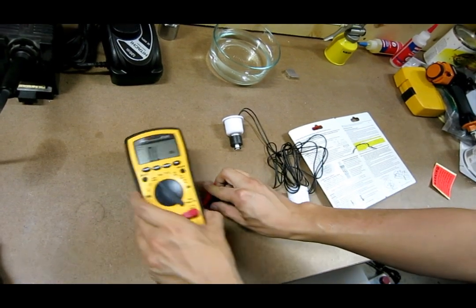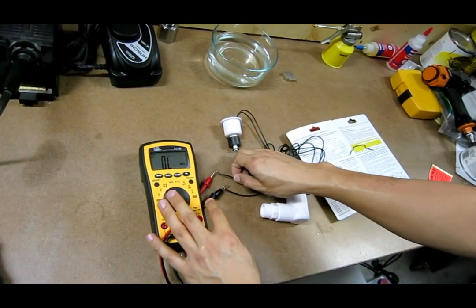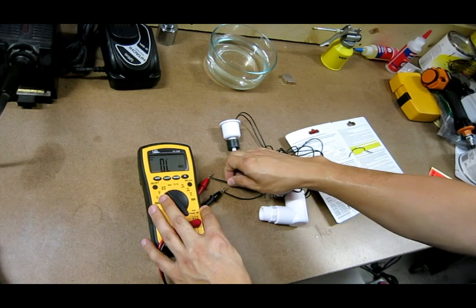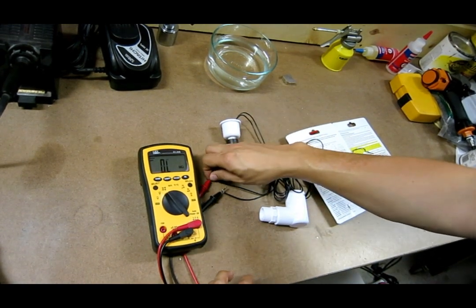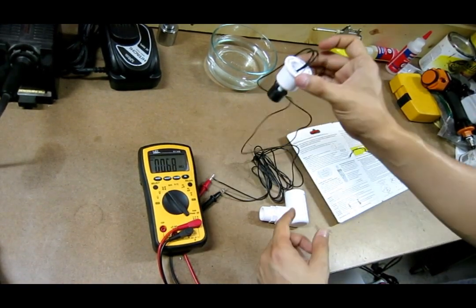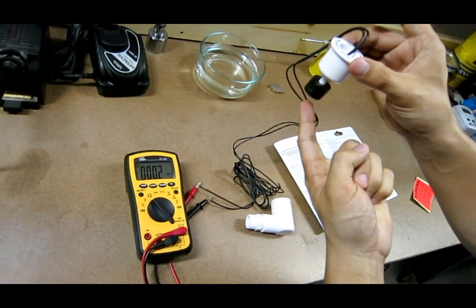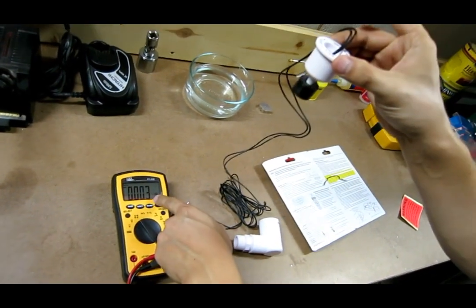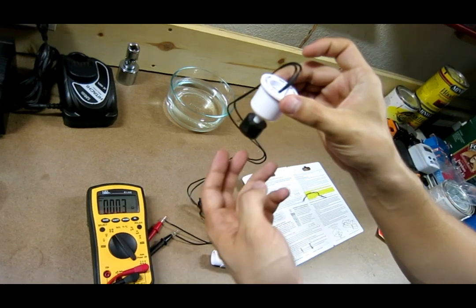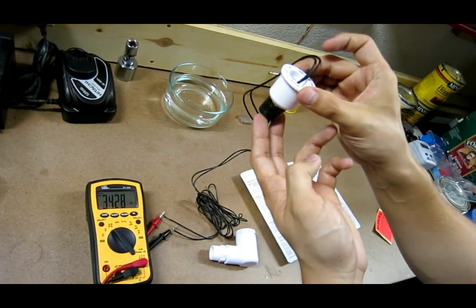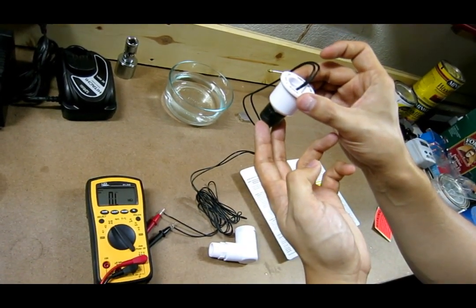Alright, I have these two lines that hook up to it. So you can see when this bobbles down, when this sits flat, it's shorted at two ohms. And when this floats up, it goes to a complete open circuit.